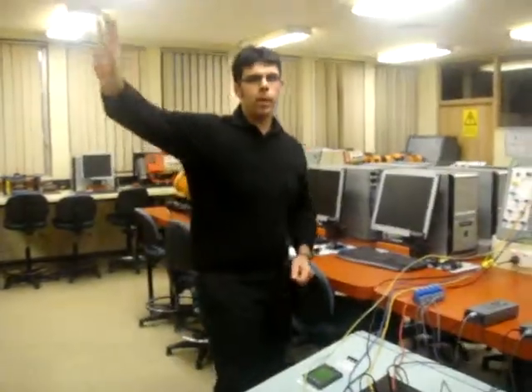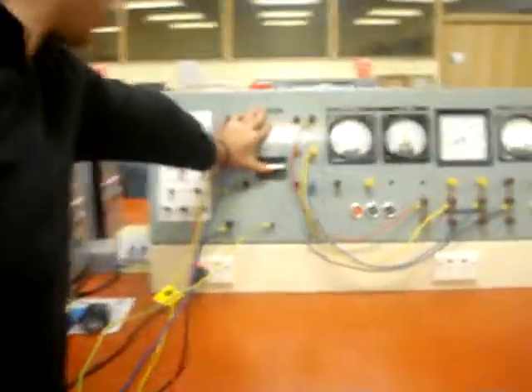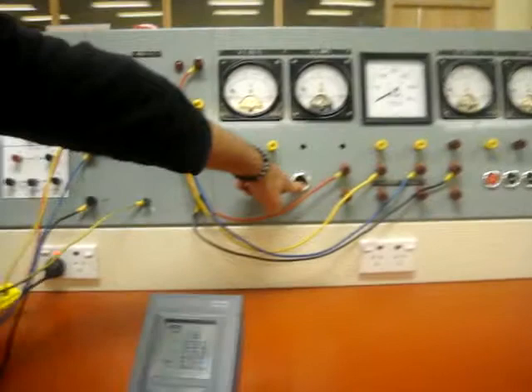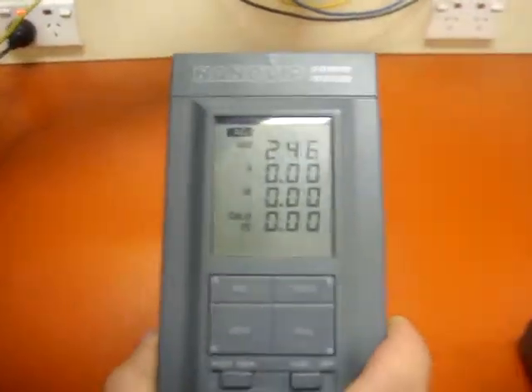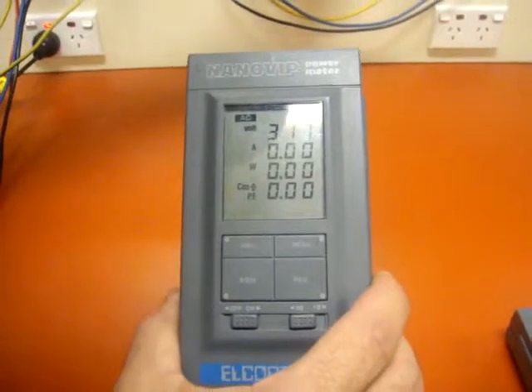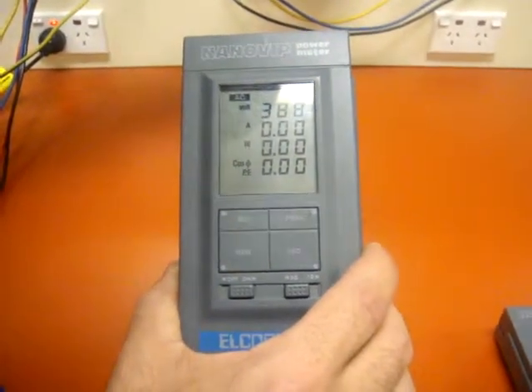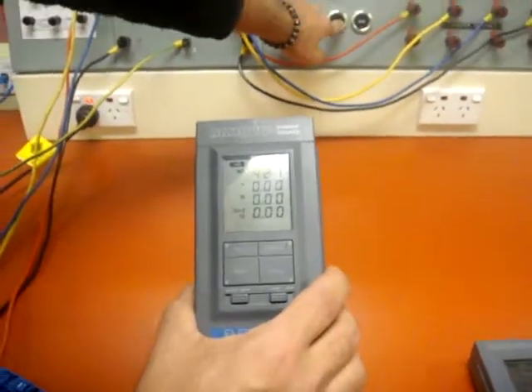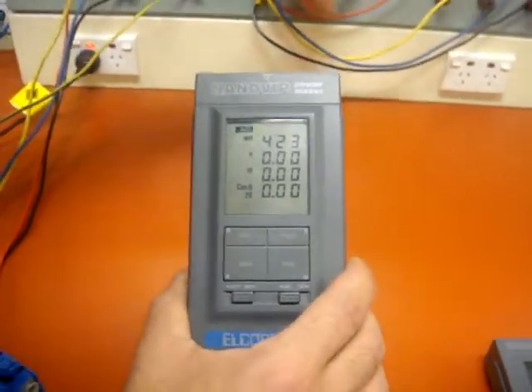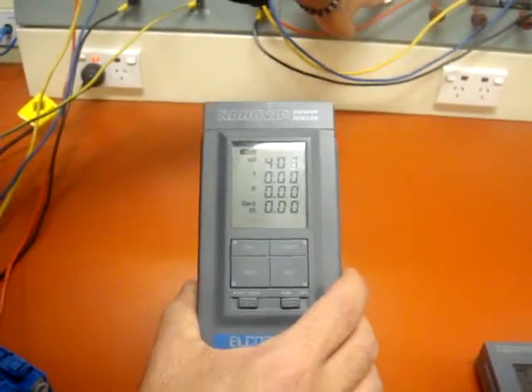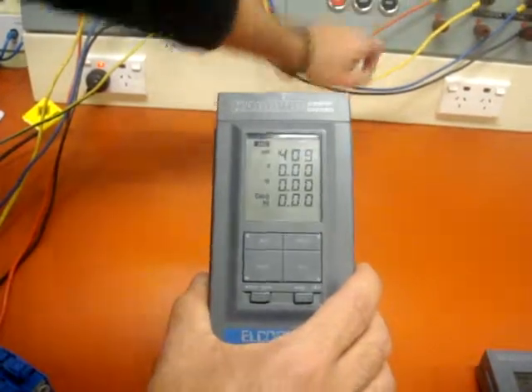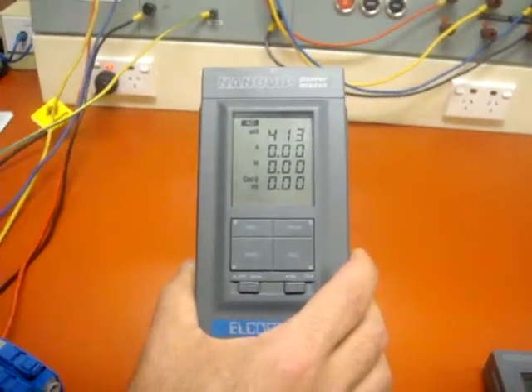Since we have now activated power to our main panel, we must switch on the circuit breaker on the transformer bank. At this point in time, note that we have a 3-phase configuration via the red and yellow phase. We will now raise our voltage to about 415 volts. We just have to wait for the voltage to get to 415.